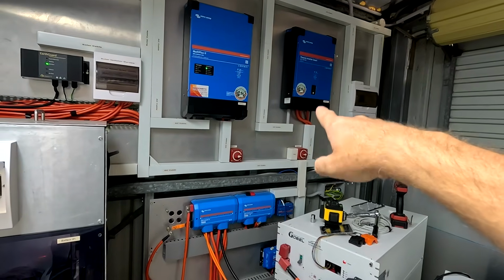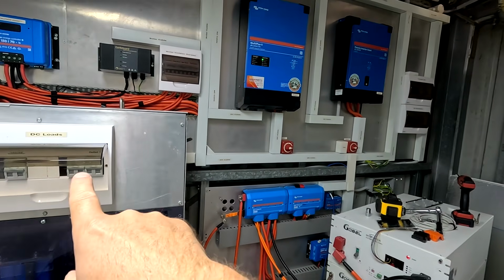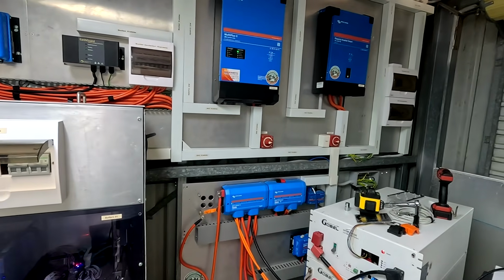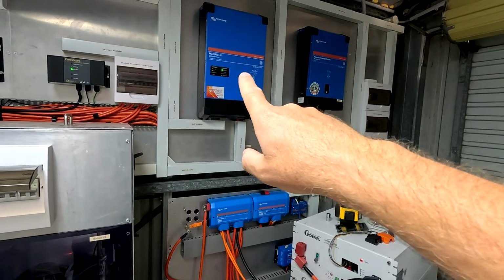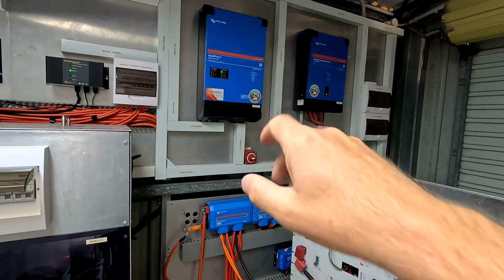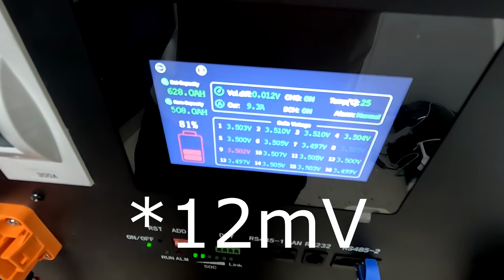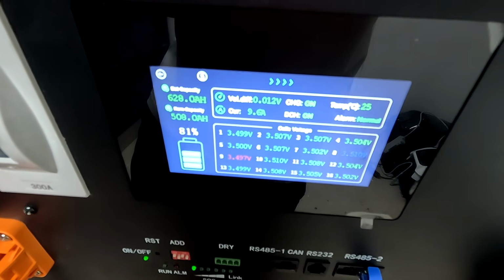So this inverter is basically connected before we hit the 63 amp limit. So 2 kilowatt there, 3.5 kilowatt there, should roughly give us 100 amps of discharge current for this battery then. Is it looking? 12 millivolt deviation. That is at 56 volts.